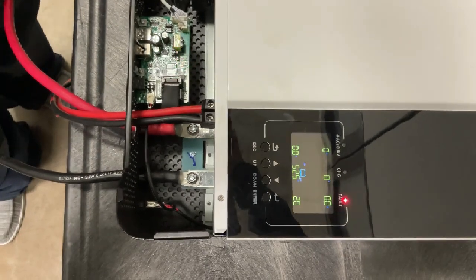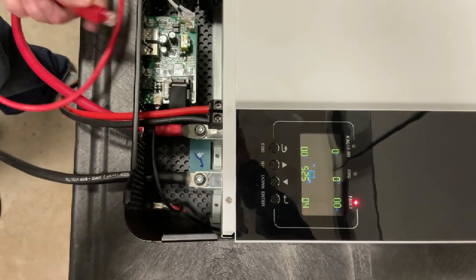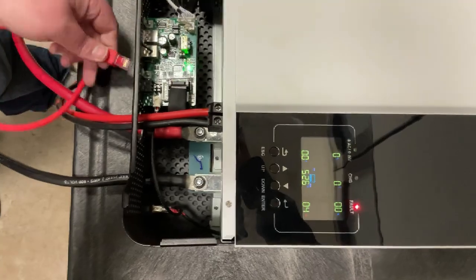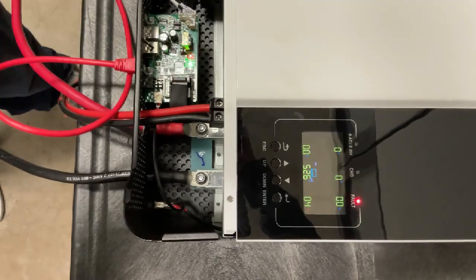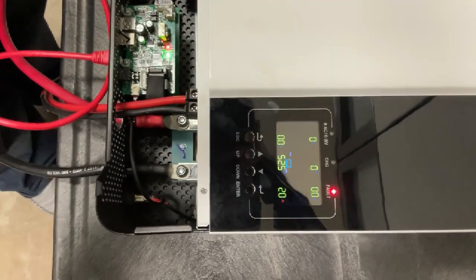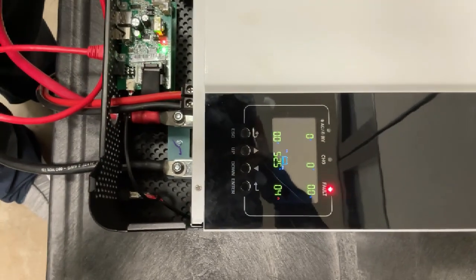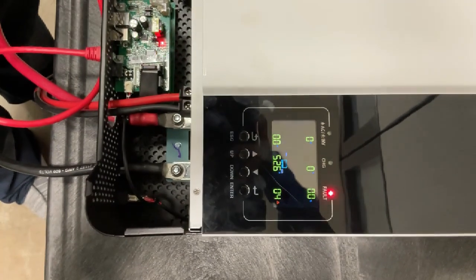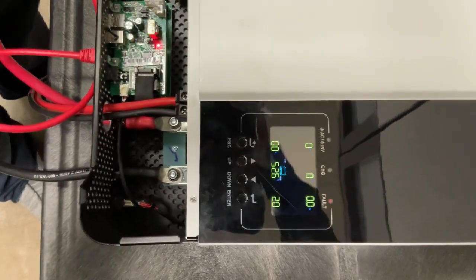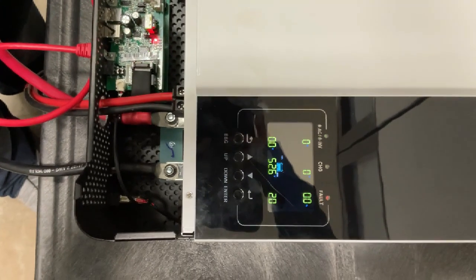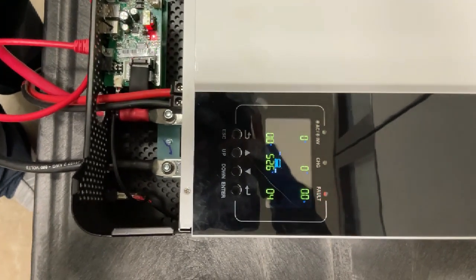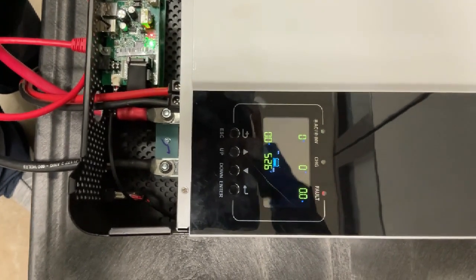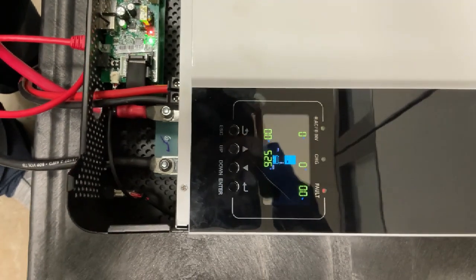As stated, there are the errors. So once that happens, simply plug your cable back in, wait for 15 seconds and both errors will clear and you will then have confirmed for yourself that you are in fact BMS communicating with your batteries. Errors have now cleared.